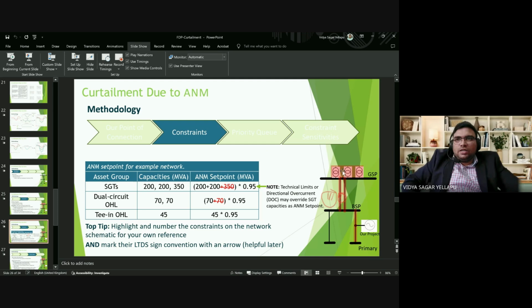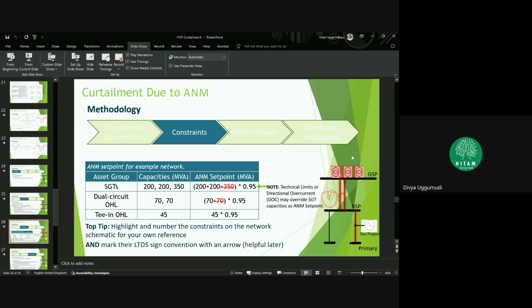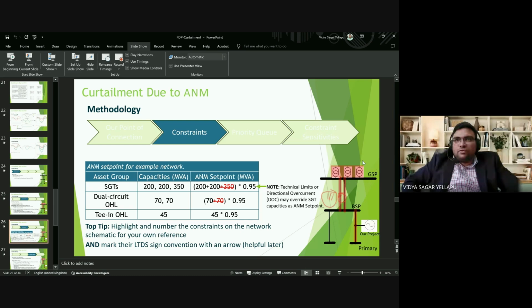Suppose there are 3 transformers here, with ratings of 200, 200, and 350. In order to represent the worst case scenario for these transformers, that is, the worst case capacity available with this GSP, we consider the loss of the highest rated transformer. In that case, it will face the worst case scenario. So this GSP is now left with a 400 MVA rating, multiplied by this derating factor.